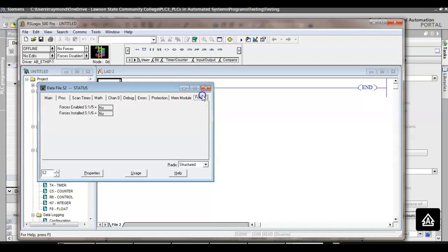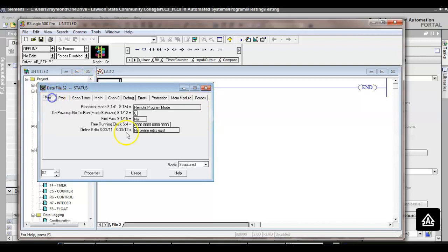So I've already got a force table built up. Well, in Siemens, you don't sacrifice all that force information unless you enable that feature. So we'll try to show y'all how to do that, because that force feature is a really neat feature, because that gives you the ability to check things out without having inputs wired up to your PLC. But remember, if you use that force feature, you're overriding the safety features built into your system. So you got to be really, really careful with that.